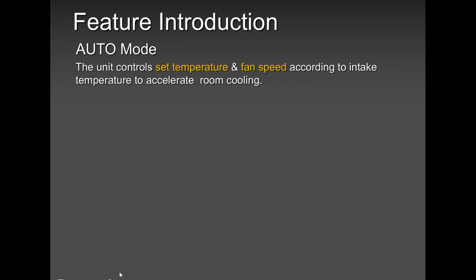Auto mode. So guys, always talk to your customer, always talk to your homeowner, about the difference between auto mode and auto fan and auto louver. Okay, this is auto mode. Auto mode functions very well in a single zone. On a multi-zone, you will always have complaints from your homeowner. It's not a good idea to use auto mode in multi-zones. But in single zone, it's a good idea.